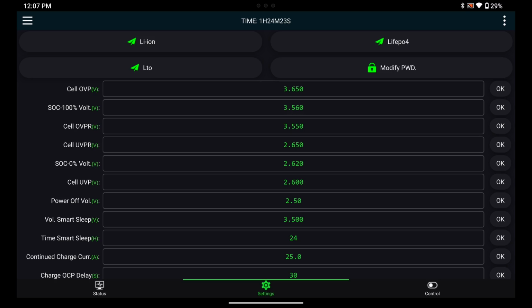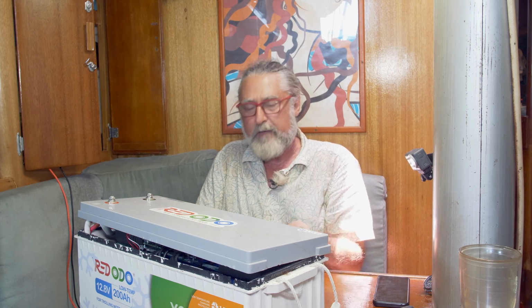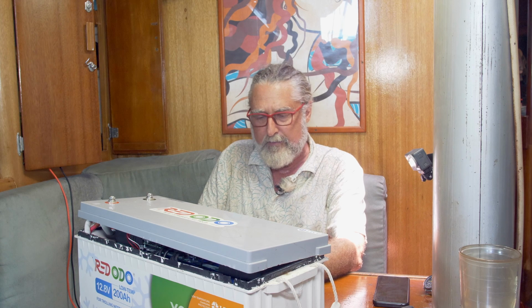The BMS also protects at the low end, so that's the under voltage section. The cell under voltage protection will happen at 2.6 volts, which would be 10.4 volts at the poles, more or less. When the first cell hits 2.6 volts, it shuts down. Much like the other setting, it's got a slightly higher voltage where it will bring that back on, allowing you to discharge again once the voltage comes up above that second number.